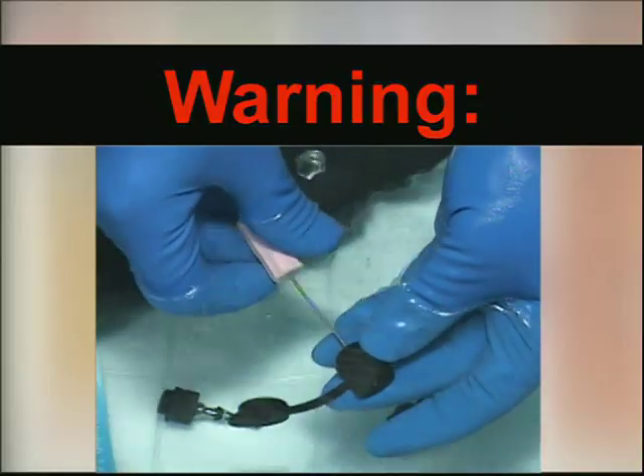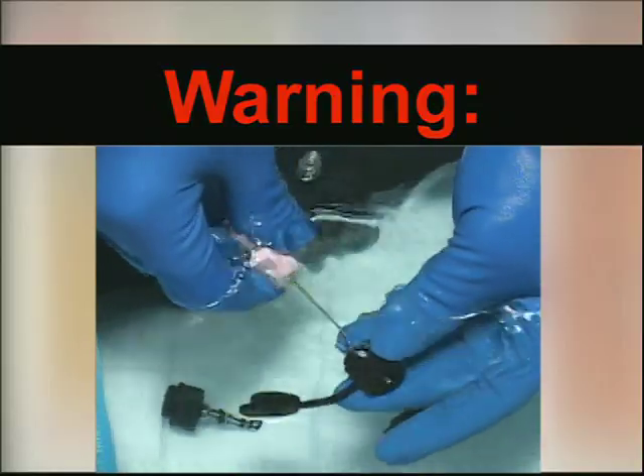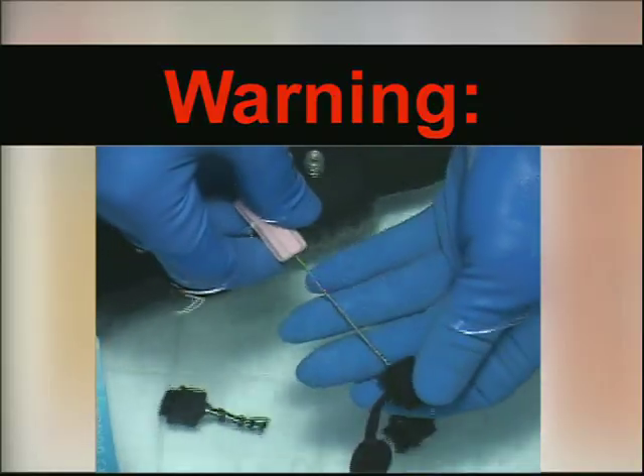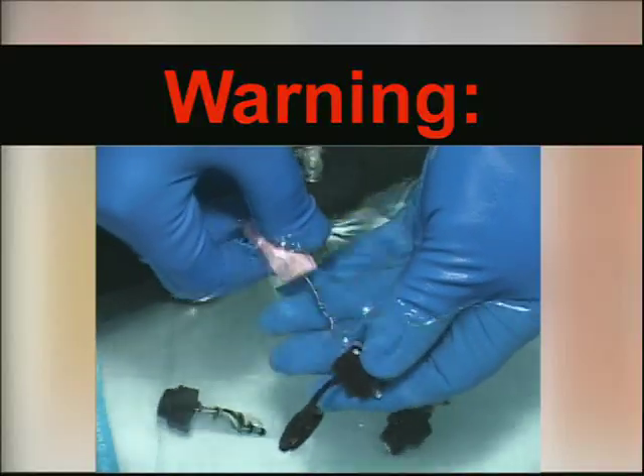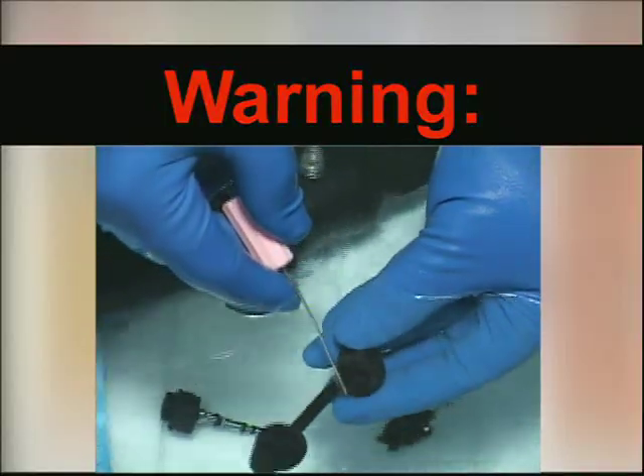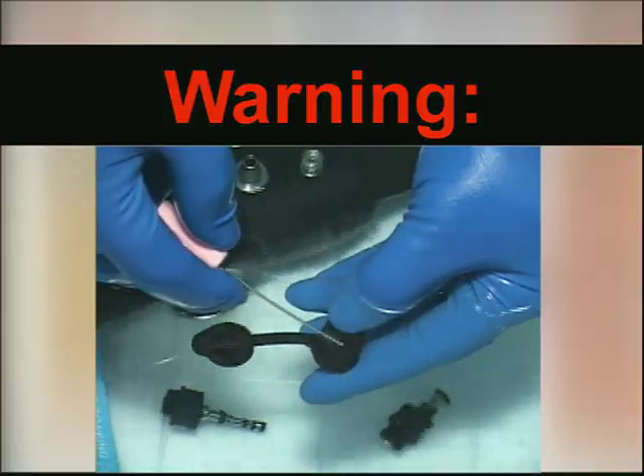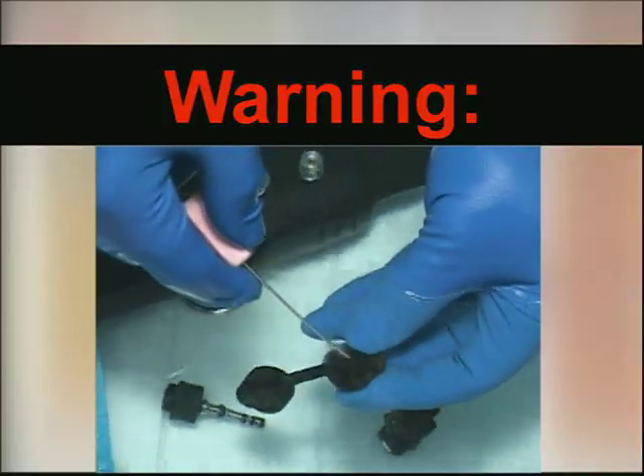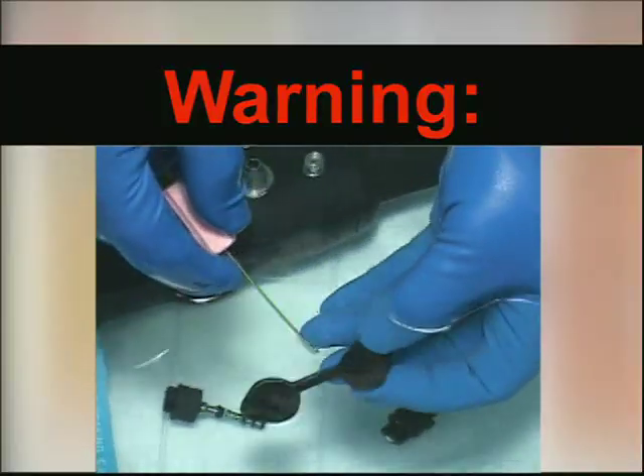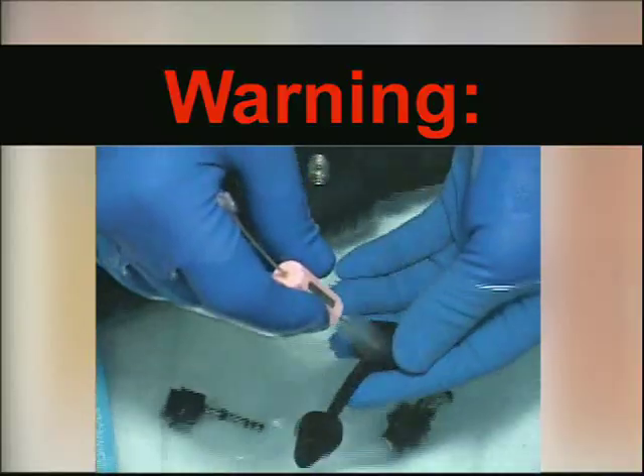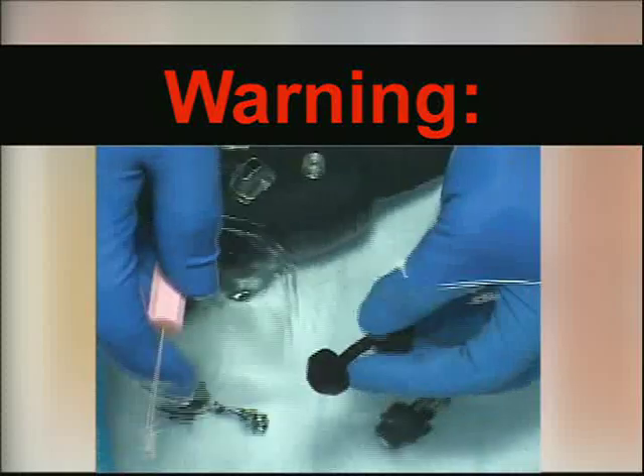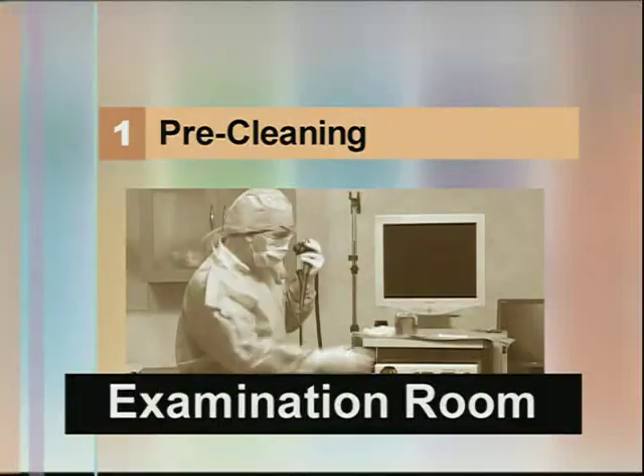Warning: the importance of meticulous mechanical cleaning of the endoscope and its removable components cannot be overemphasized. Prior to disinfection or sterilization, all instruments and components must be scrupulously cleaned. Failure to do so could result in incomplete or ineffective disinfection or sterilization. Pre-cleaning in the examination room.